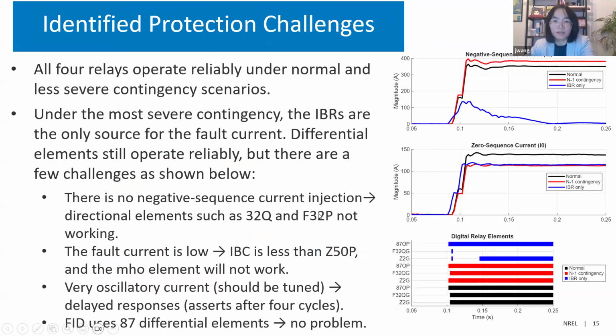Due to the time, I will only summarize what we have learned from this study. For all 4 relays, they can operate reliably under normal and N-1 contingency scenarios. Under the IBR only scenario, the most severe, the differential elements still operate reliably, but there are a few challenges as shown below. As you can see here, for the normal and N-1 scenarios, the negative sequence current is very high, so those protection relay elements still operate reliably. But under the IBR only scenario, the negative sequence goes up and then dies down. The relay couldn't make the right decision. And you can see the 32QG, Z2G elements didn't operate. It goes high in the beginning because the negative sequence is high, but then it got disordered.